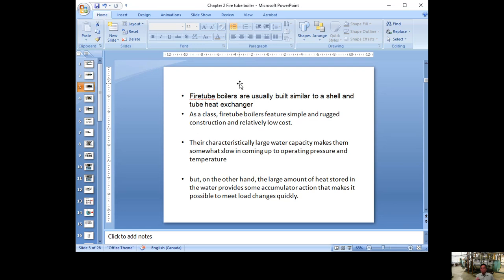The fire tube boiler looks like a shell with a couple of pass changes. You cap both ends with a front door and back door, and you get a fire tube boiler — really simple and rugged construction. The cost is low because every tube is straight; you don't have to bend it. One key characteristic is that the water is on the outside of the tubes, so the volume of water is quite large.